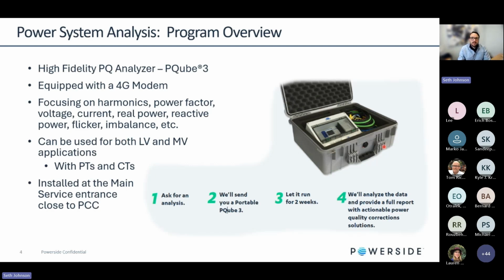So first, I'd like to talk about the overview of the program. I mentioned earlier that the Alameda business manufactures power quality analyzers, and it's a very high fidelity power quality analyzer, a Class A device from a hardware perspective, which can do various functions, but looks at well over 3,000 different parameters at any given time. It offers trending data, and it also does waveform capture. So when there's an event detected or a power anomaly, such as a voltage sag or a transient or a high inrush event, you can trigger an event with the PQ3, which captures the waveform at 512 samples per cycle. So it's very precise in terms of its capabilities.